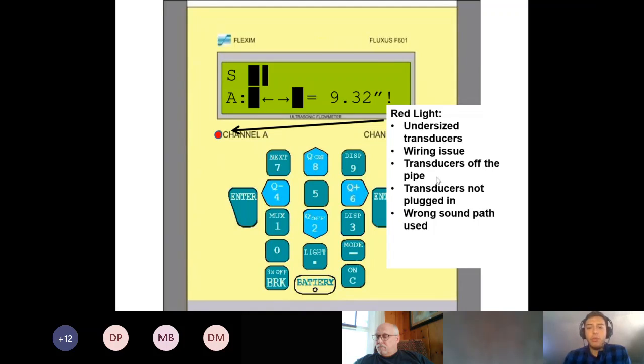And then maybe you could be using the wrong mounting. So if you're doing a 2 sound path and you have it in a direct mount, so on either side of the pipe, it's not going to read because it's bouncing the ultrasonic beam off the back wall and trying to communicate with another transducer on the same side of the pipe, but it's not there. So just verify your sound path as well.